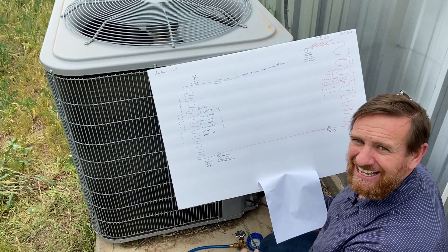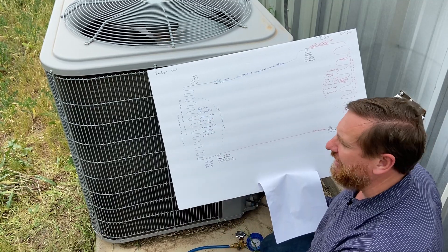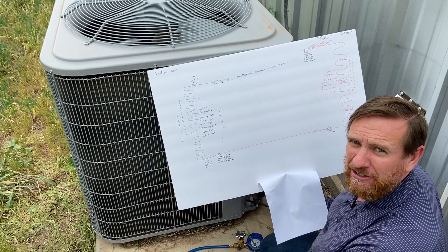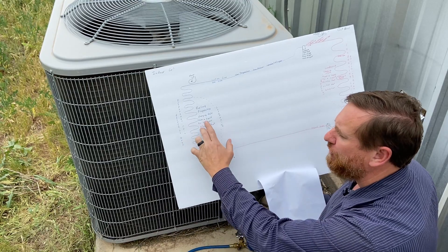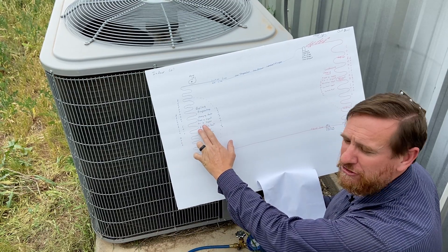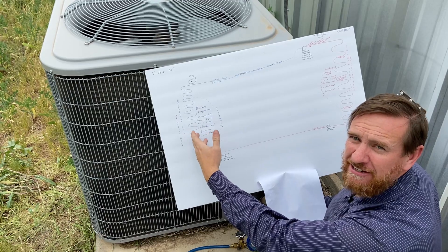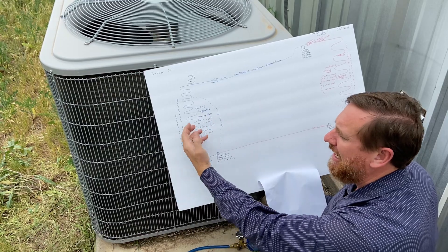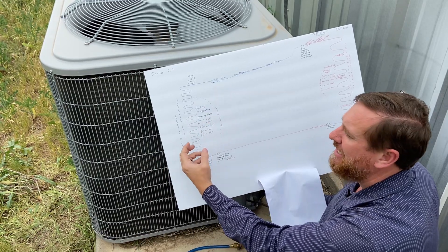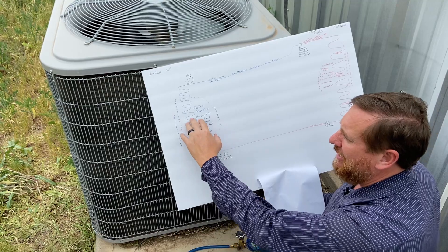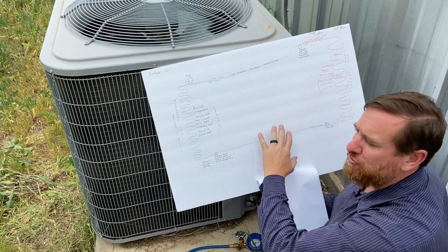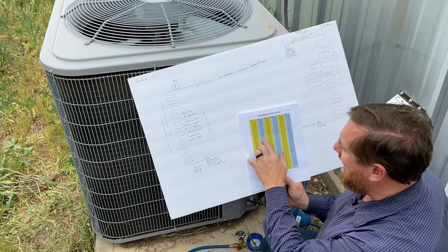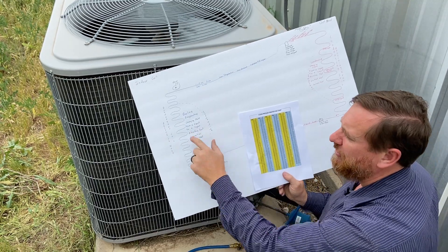The air temperature inside is 75 degrees. So there's 75-degree air going across a 52-degree evaporator. The heat leaves the air and goes to the cooler refrigerant, causing it to boil and change state from liquid to vapor, and we continuously pull in more and more heat as we move air across this evaporator coil. The majority of that evaporator coil is at 52.5 degrees Fahrenheit.